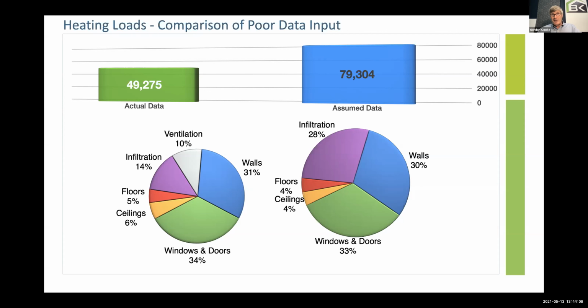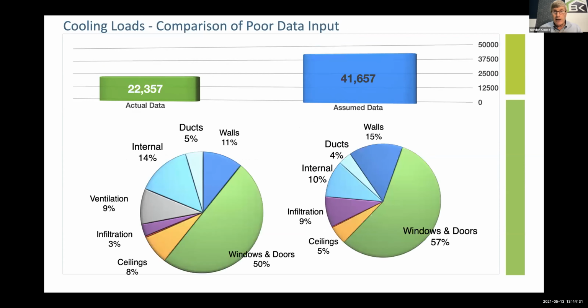The one on the right, the 79,000 BTUs, well, 80 is a little light, so I'm going to go to 100. And if I went to 100,000 BTUs, because I'm oversizing slightly, and the actual heat loss is only 49, the furnace is actually twice as big as it needs to be. So oversize by furnace selection, don't oversize by fudging numbers, is really the point. And of course, somebody's going to say, but I need a larger furnace, a larger air handler in order to get me my cooling loads.